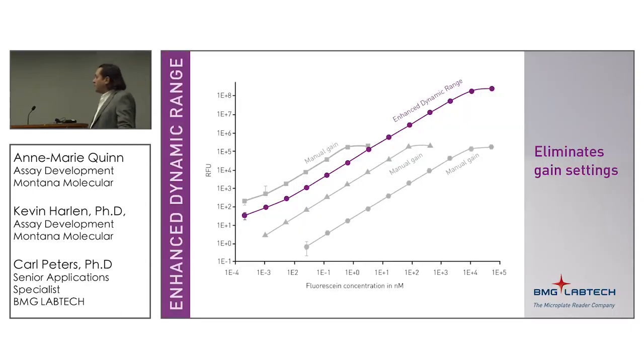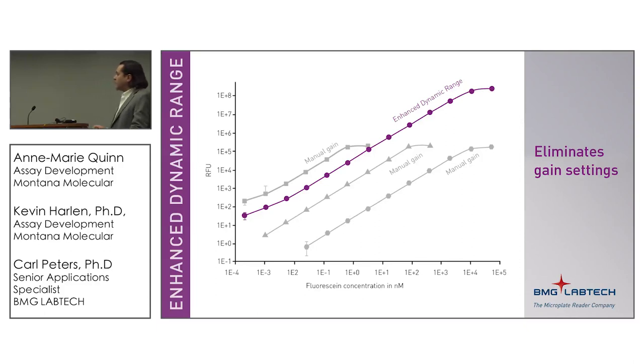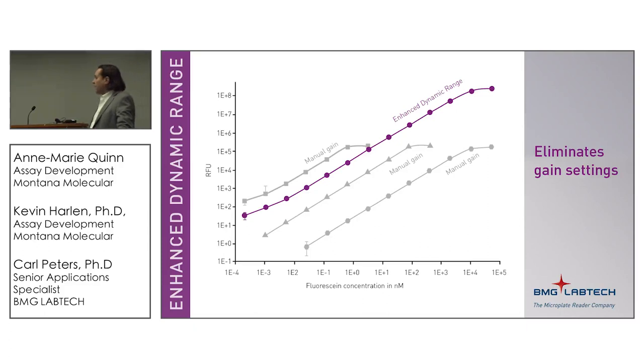Typically, to see the entire range of concentrations over a broad range, you would have to use several different manual gains. With the enhanced dynamic range on the ClarioStar Plus, you do not have to worry about gain settings at all — just read the plate and all the data across the concentrations comes out.